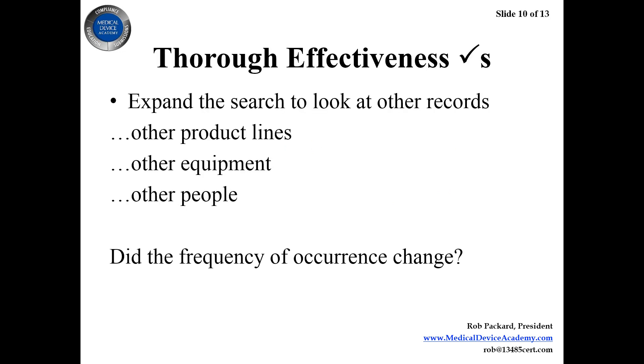To do a thorough effectiveness check — for example when re-auditing a process — you need to expand your search to look at other records, just as you would during root cause analysis. You're going to look at other product lines, other equipment, and other people. If you have one production line making a certain type of knee implant and you implement the corrective action there, but the same process exists on another line making a different knee implant, your CAPA won't be effective if you didn't implement the same corrective actions on the other line. A good effectiveness check looks beyond where the problem originally occurred.